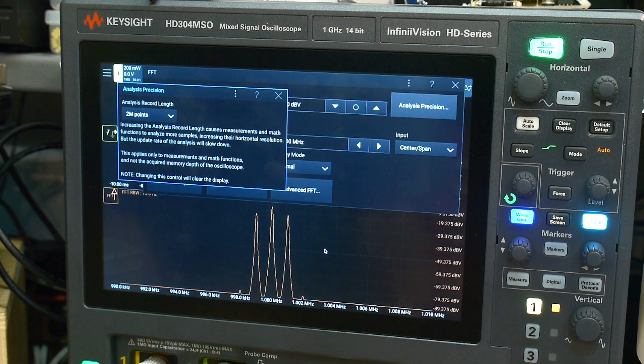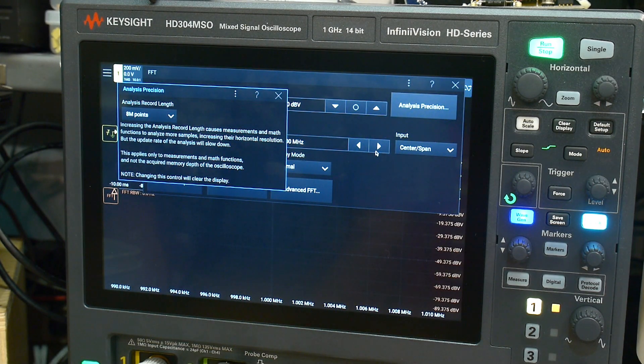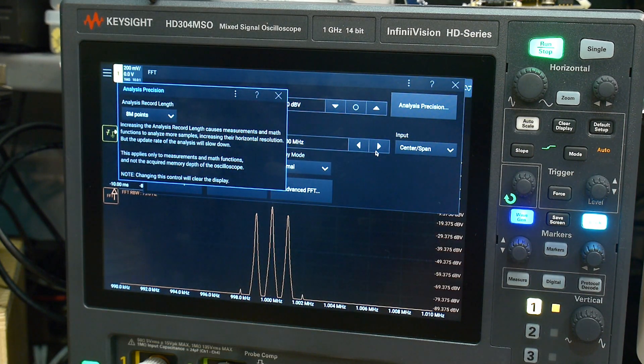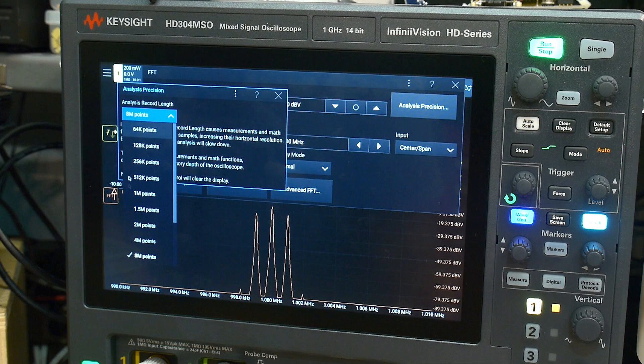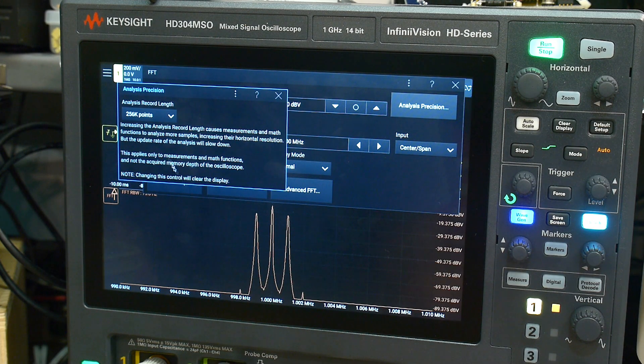Let's do 2 million just to see how slow that is. That's not too bad. Everyone's going to say, well, do 8. Okay, we'll do 8 — see how it goes. It's going to take a while. There you go. I mean, that is not bad for 8 million data points. That helps you with signal-to-noise to be able to see things way down in the mud. Setting it to 256 — that's a pretty good sample right there.